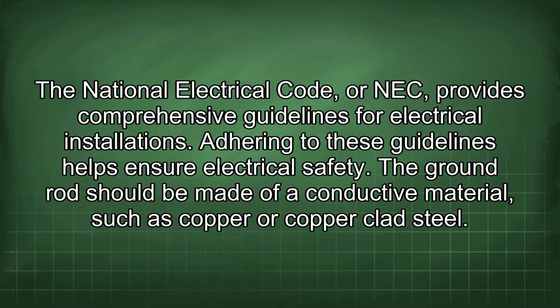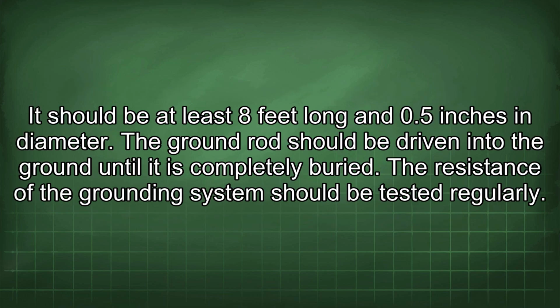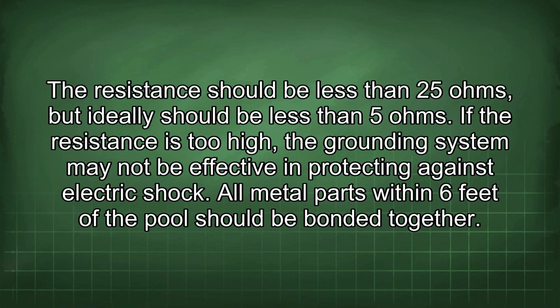The ground rod should be made of a conductive material, such as copper or copper-clad steel. It should be at least 8 feet long and 0.5 inches in diameter. The ground rod should be driven into the ground until it is completely buried. The resistance of the grounding system should be tested regularly. The resistance should be less than 25 ohms, but ideally should be less than 5 ohms. If the resistance is too high, the grounding system may not be effective in protecting against electric shock. All metal parts within 6 feet of the pool should be bonded together.